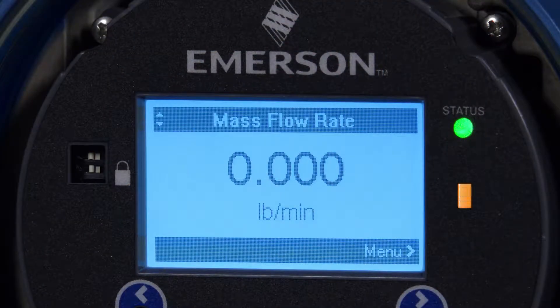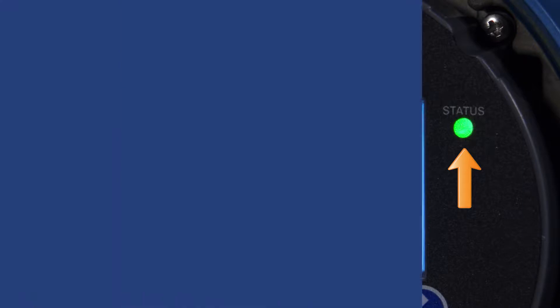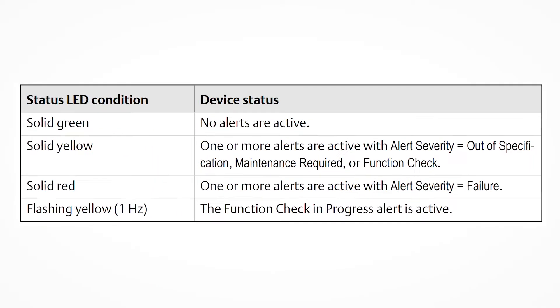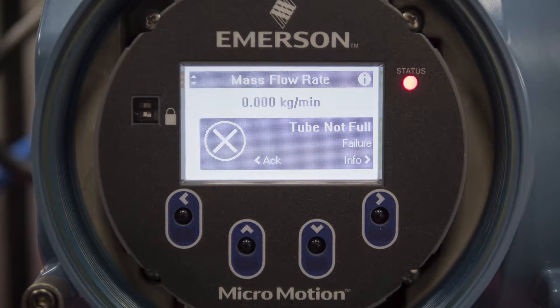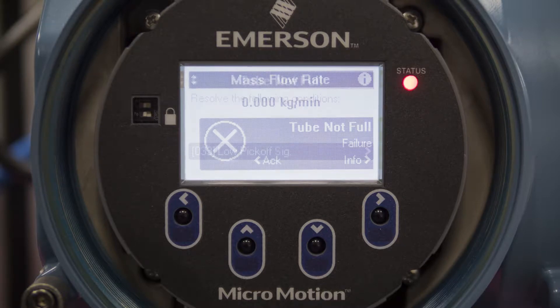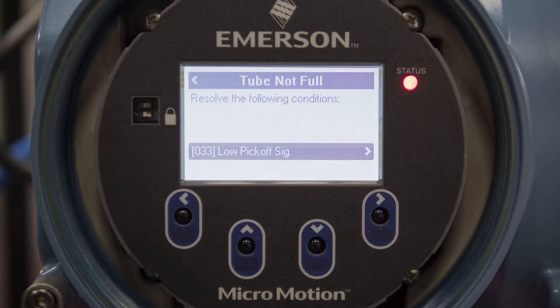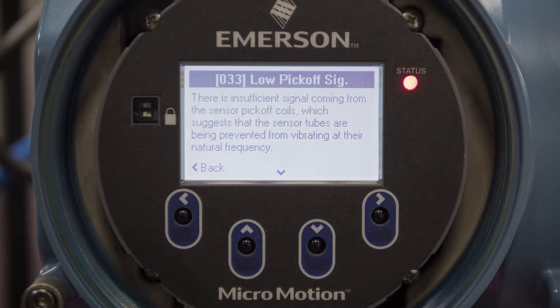Second, check the status LED on the transmitter and use the following table to determine the device status. The ideal LED status is solid green, which indicates that no alerts are active. If necessary, check the active alerts using the display. The display of the 5700 transmitter will show the alert code, along with an explanation for the alert and the course of action.